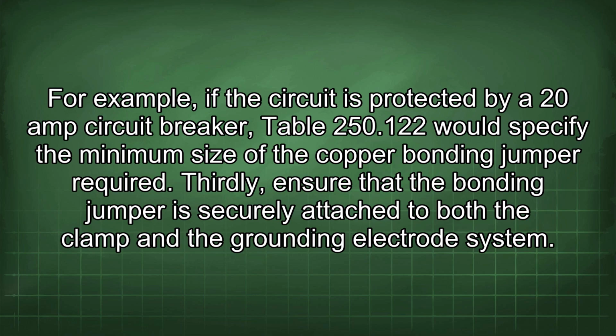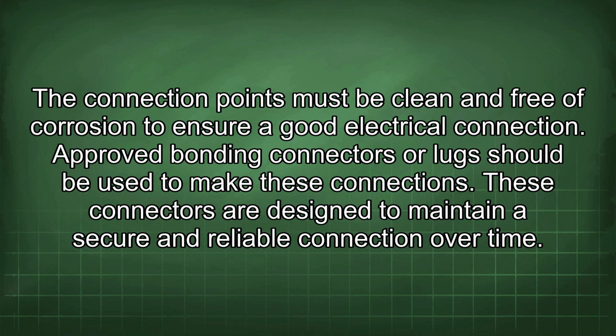Thirdly, ensure that the bonding jumper is securely attached to both the clamp and the grounding electrode system. The connection points must be clean and free of corrosion to ensure a good electrical connection. Approved bonding connectors or lugs should be used to make these connections. These connectors are designed to maintain a secure and reliable connection over time.